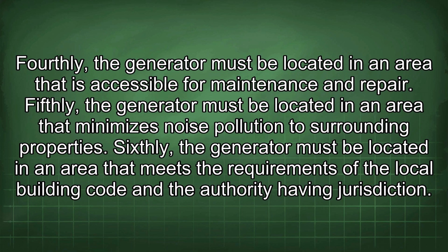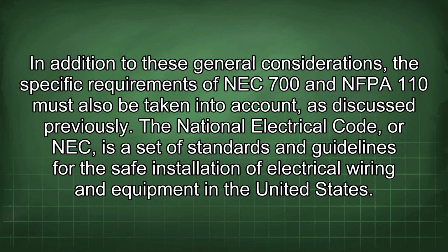Sixthly, the generator must be located in an area that meets the requirements of the local building code and the authority having jurisdiction. In addition to these general considerations, the specific requirements of NEC 700 and NFPA 110 must also be taken into account, as discussed previously. The National Electrical Code, or NEC, is a set of standards and guidelines for the safe installation of electrical wiring and equipment in the United States.